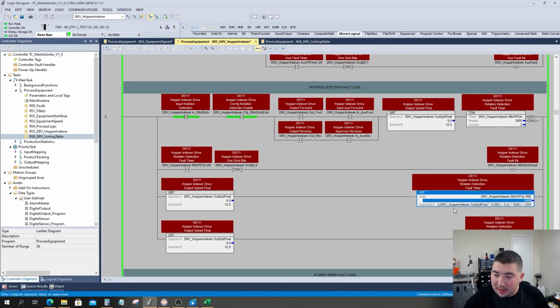The preset is a negative relationship based on our output speed, and I did a little bit of calculations on a piece of paper to find the correct slope, and all we're doing there is determining our slope factor for our relative time. We're changing that to an integer value in milliseconds, so that's what the multiply by 1,000 is for, and then we add a little bit of a fudge factor, and this is going to allow it to give a little bit more of a buffer of 1.2 seconds, and this will calculate a new timer based on our actual speed. That way the system can be more accurate with a fault timer, and rather than just an arbitrary timer like 2 seconds, it can actually react to the different speed commands of the program.